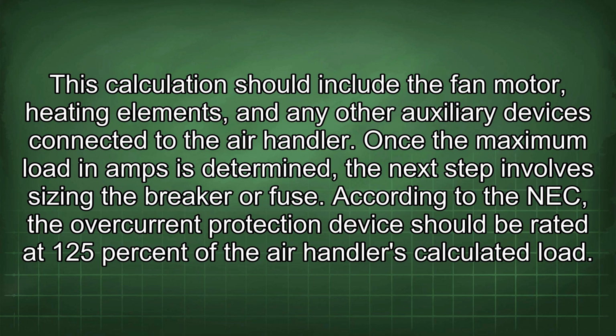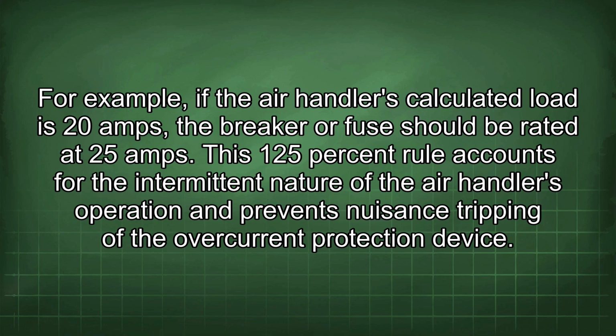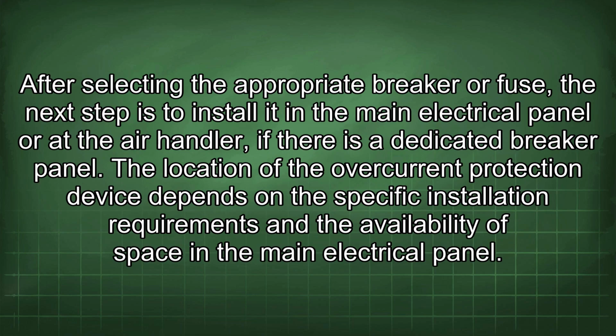Once the maximum load in amps is determined, the next step involves sizing the breaker or fuse. According to the NEC, the overcurrent protection device should be rated at 125% of the air handler's calculated load. For example, if the air handler's calculated load is 20 amps, the breaker or fuse should be rated at 25 amps. This 125% rule accounts for the intermittent nature of the air handler's operation and prevents nuisance tripping of the overcurrent protection device.